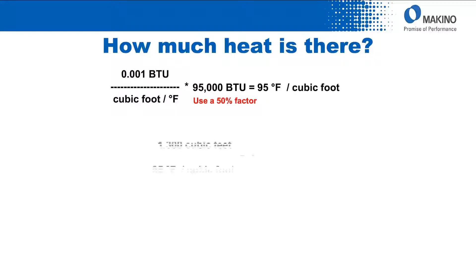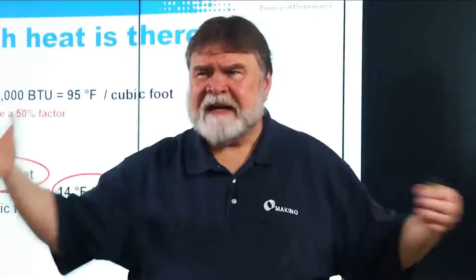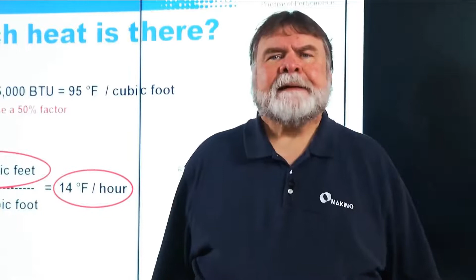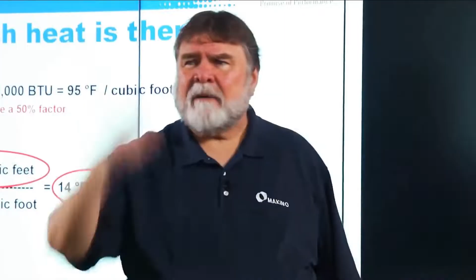Again, remember that PS105 is about 1,300 cubic feet. So with that factor, if I had that machine in that room, 12 by 12 by 9, and didn't do something to get rid of all that heat, I would raise the temperature by 14 degrees Fahrenheit for every hour that I ran the machine. So over an 8-hour shift, that's 112 degrees.